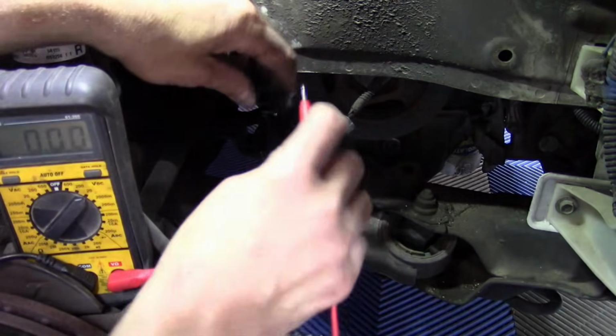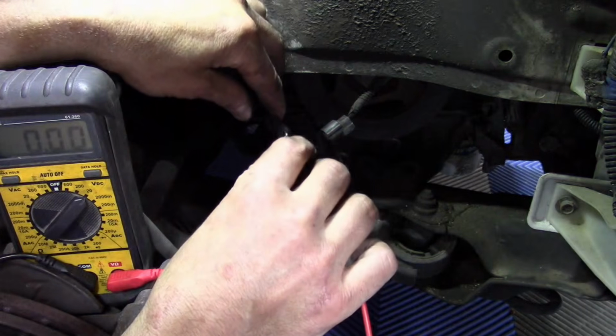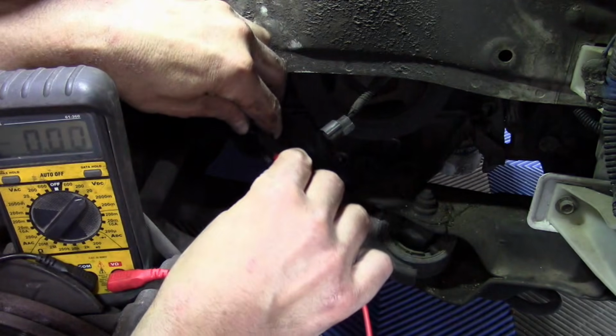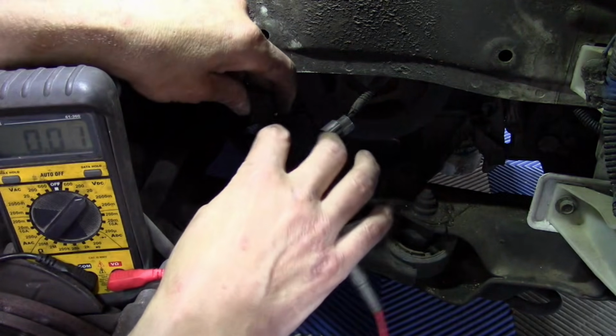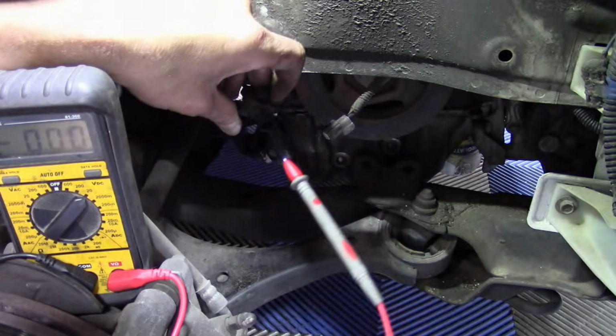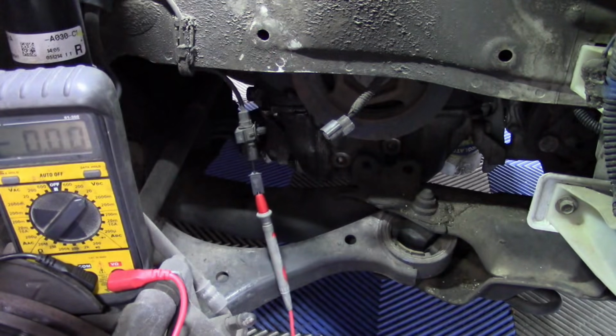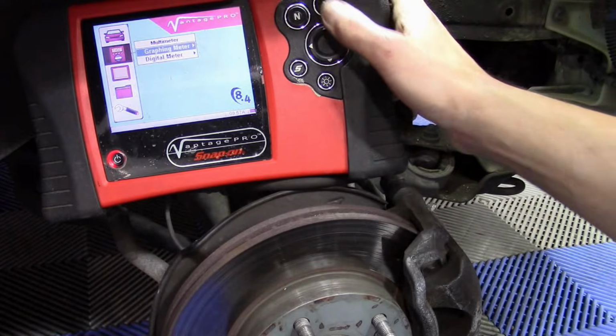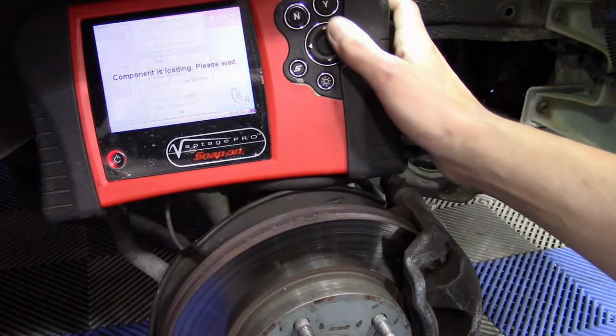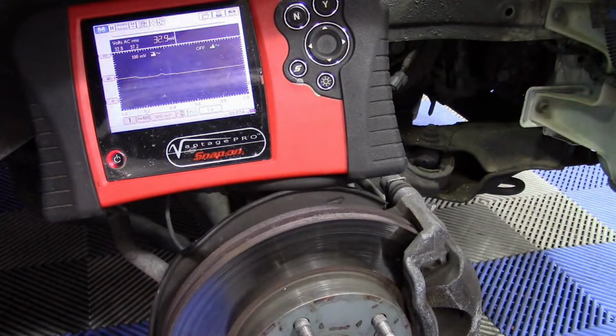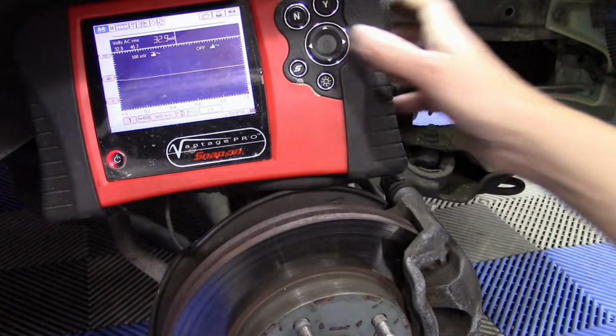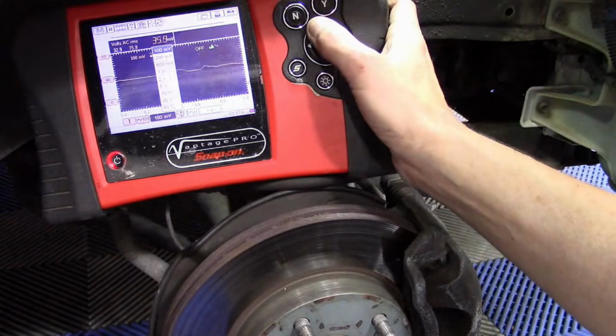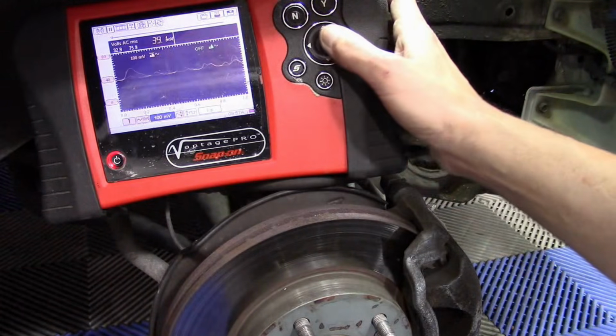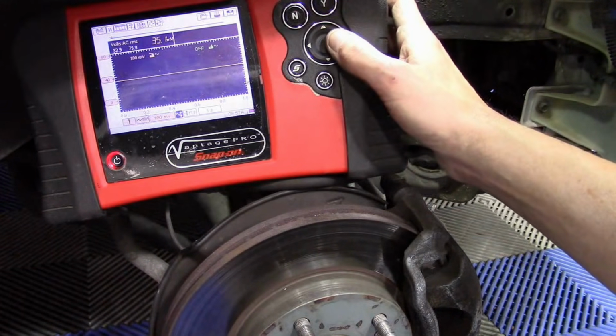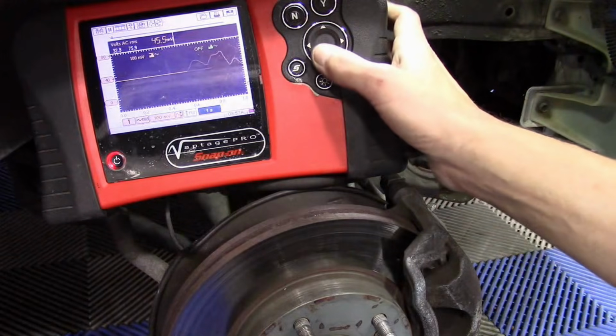So what we're going to do is connect our leads up to the sensor. I'm using a special long insulated probe so I don't cross my leads and get a false negative reading. We're going to go to a graphing multimeter here, volts AC. You want volts AC, because this is actually going to put out an AC voltage. We want to be on our lowest scale because we're not going to be turning this very fast by hand, and a 1 second scale is pretty good.